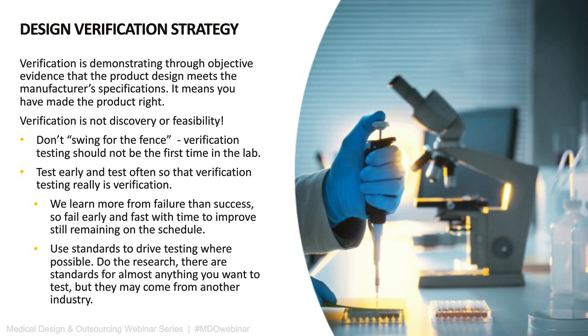So how do you optimize your design verification? Well, you have to develop a strategy that gets you through verification. I can give you a little bit of a definition. Verification is demonstrating through objective evidence that the product design meets the manufacturer's specification. When you verify a product, it means you have made the product correctly. It meets your requirements. Different than validation. I'll cover that in a minute. However, verification should not be discovery or feasibility. Verifying means that you are demonstrating that it's already there.